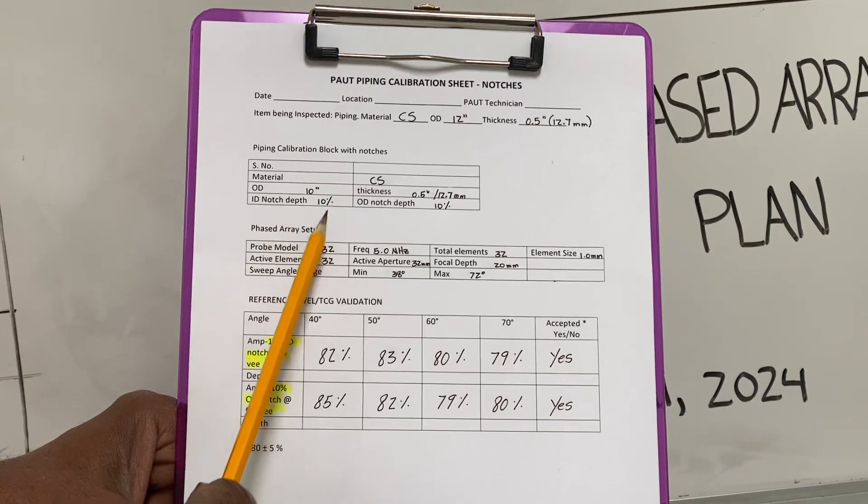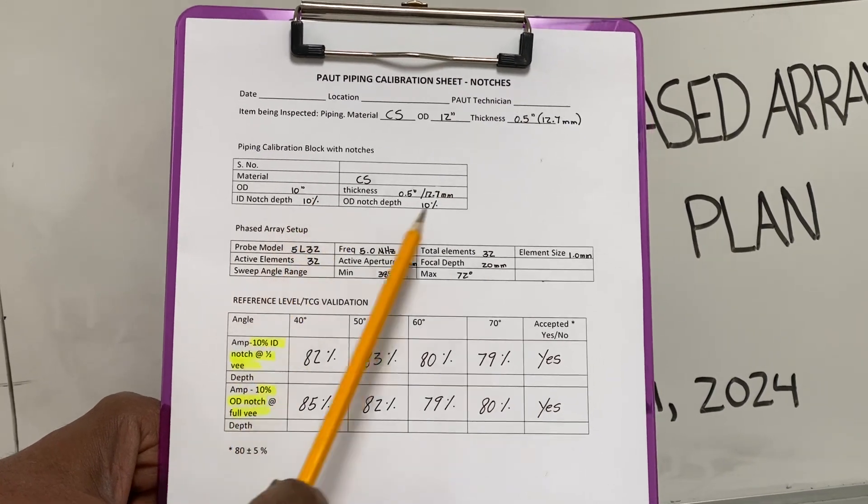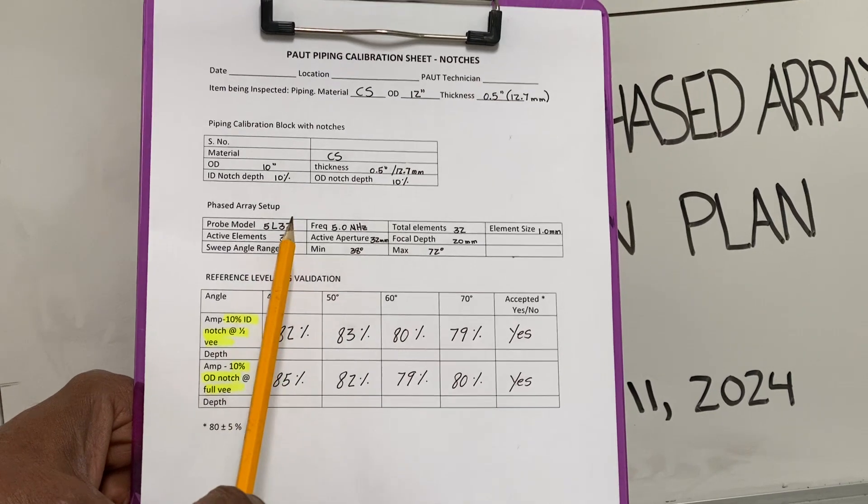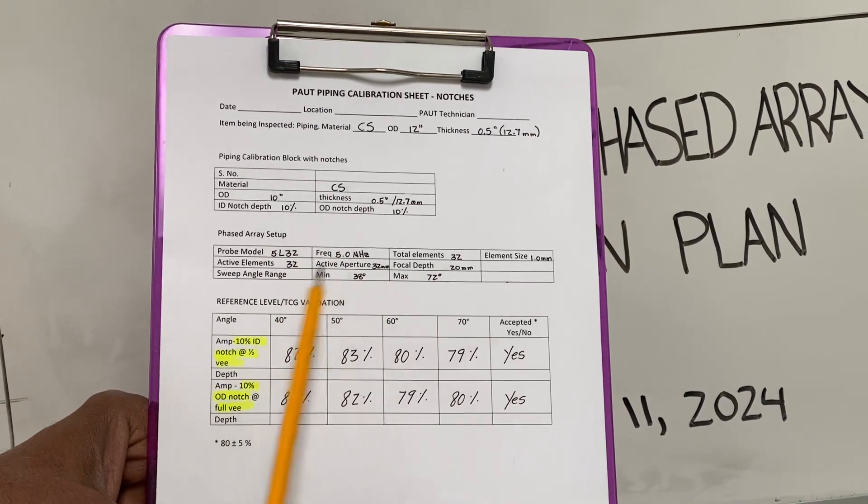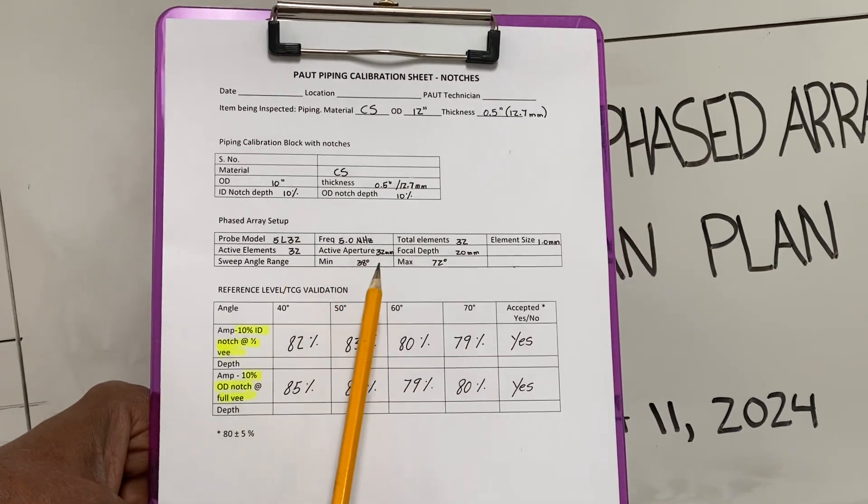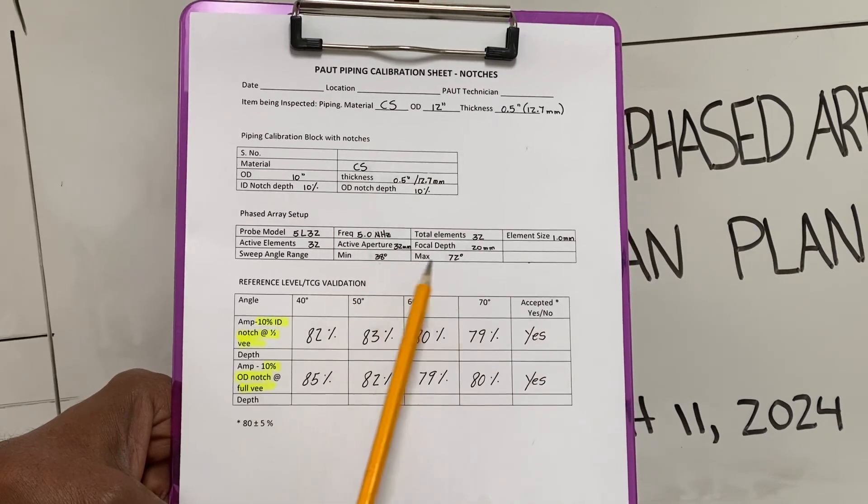For the 12 inch, we are using a 10 inch pipe with 10% notches. And here is the phased array setup, the probe, the frequency, active aperture and the focal depth. And the sweep angle is from 38 degrees to 72 degrees.